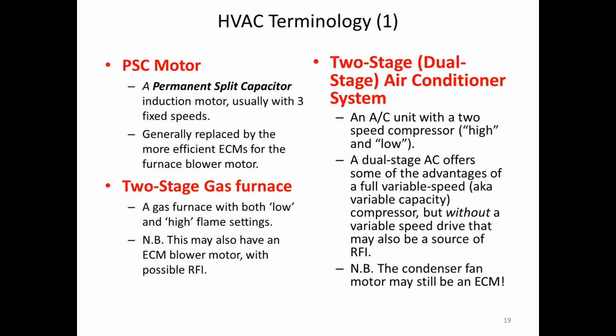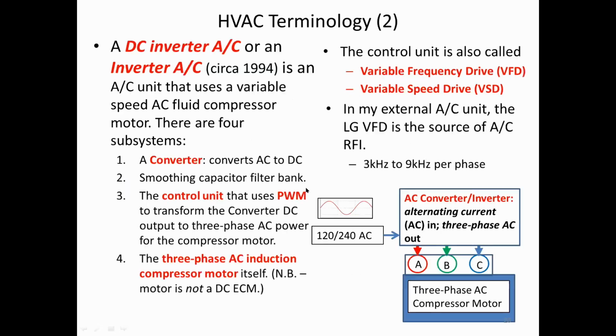By the way, the air conditioner will also have a condenser fan. And according to my contacts at Lennox, the condenser fan may be an ECM. If you're wondering why ECMs are being put into air conditioners and elsewhere, the answer is people want high efficiency, particularly in commercial settings, and may not have to worry about RFI, but we do.